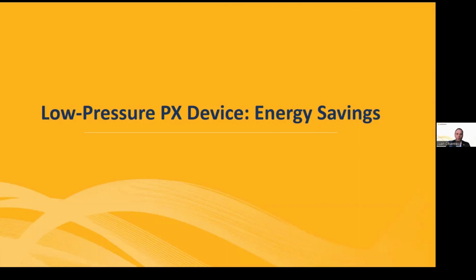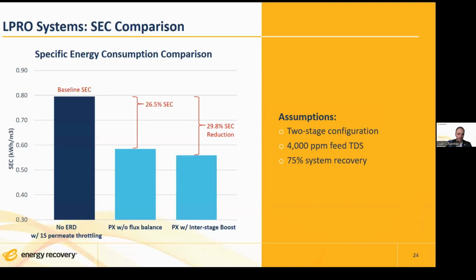And what energy savings can we expect by using the PX energy recovery device, pressure exchanger? If we go to the figures at the beginning of the presentation, in a two-stage configuration, 4,000 ppm TDS and 75% system recovery, the baseline was about 0.8 kilowatt hour per cubic meter. If we add the PX and we don't use any flux balance or interstage booster pump, we can reduce the specific energy consumption by 26.5%. But if we also add the interstage booster pump and we balance the fluxes, as we are operating at the best point of the membranes, we are reducing up to 30% of the specific energy consumption.